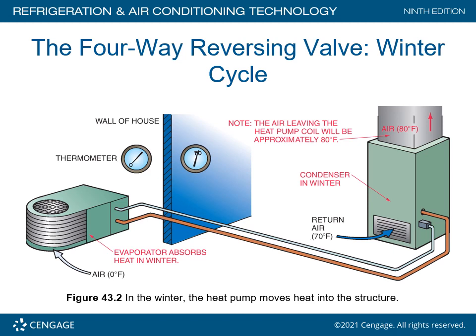One of the limitations of heat pumps is that people, especially older people with circulation issues, say that the temperature of the heat pump is not as high as a gas furnace. That is a correct statement. Typically, on a heat pump, we are going to see outlet temperatures around 100 to 110 degrees, whereas on a gas furnace, you can get all the way up to 130 degrees, but you will not see those really high temperatures on a heat pump.